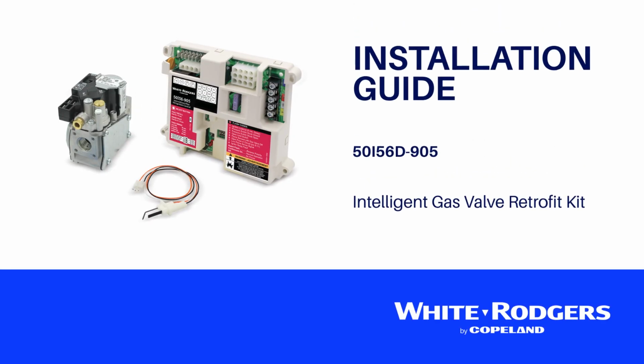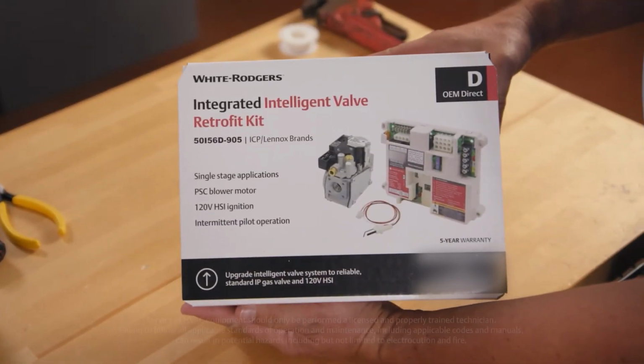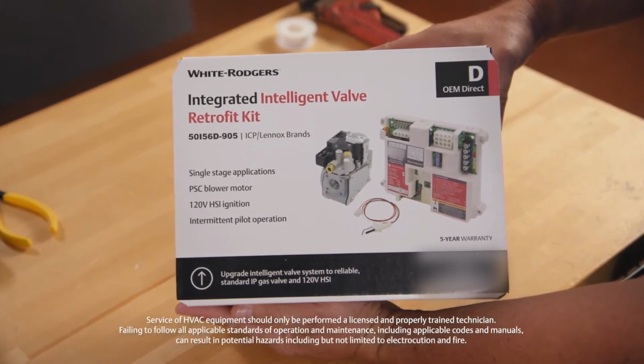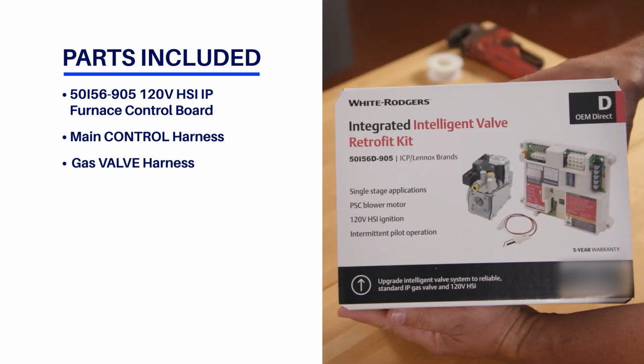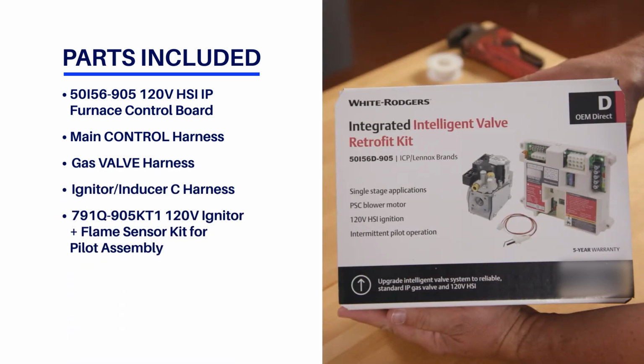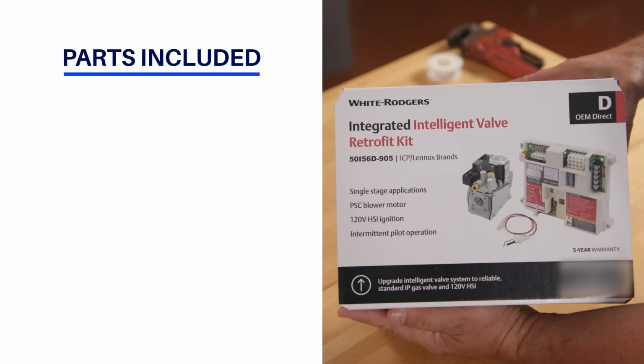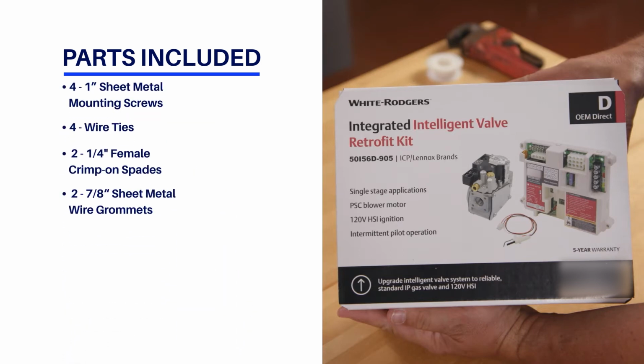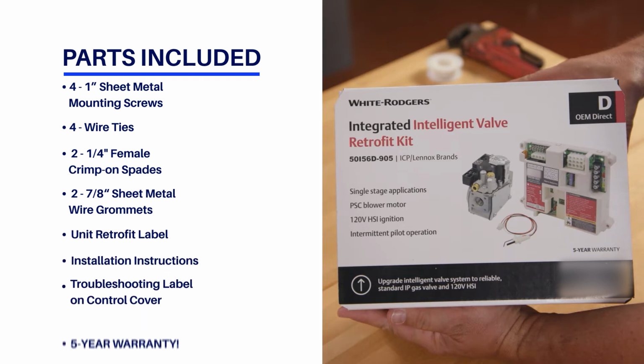This is the installation video for the White-Rodgers 50I56D-905 Intelligent Valve Retrofit Kit. The kit includes materials needed to replace or upgrade popular ICP and Lennox brand furnace control boards and utilize a standard intermittent pilot gas valve. It is designed to upgrade hot surface ignition systems using an SV9500, SV9501, or SV9502 intelligent valve and an electronic fan timer with single-stage PSC inducer and blower motors.